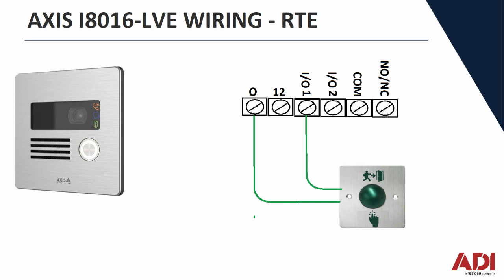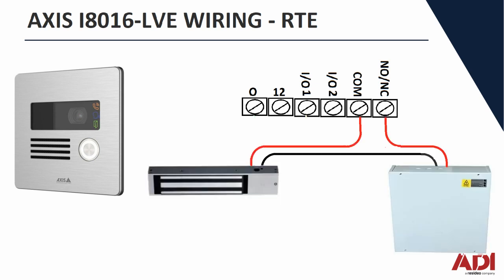If you were connecting a mag lock to this, the mag lock would require its own separate power supply, one amp, and the magnet is wired through the common and the normally open, normally closed contact. In the configuration of the software you can dictate what that output is, whether it's normally open or normally closed, fail secure or fail safe. But from the wiring point of view you simply break the positive power source to the magnet to open it, and with it being a closed contact it will send power constantly to the mag lock.